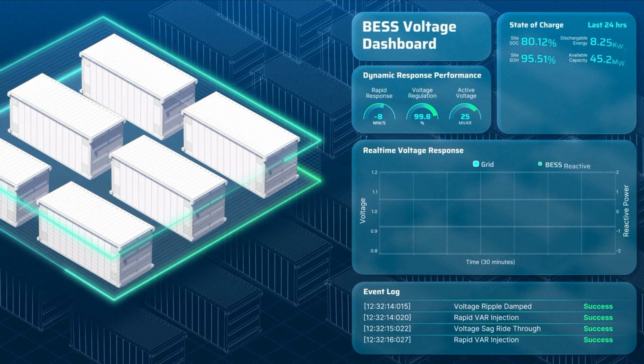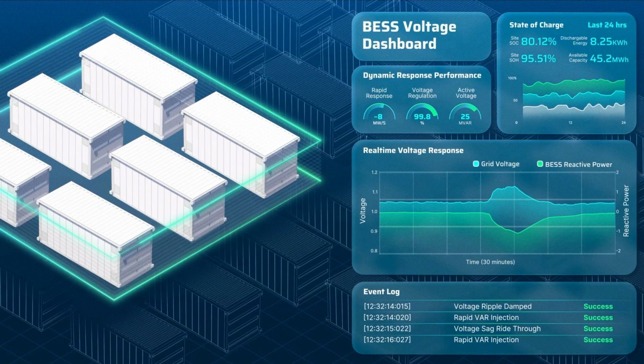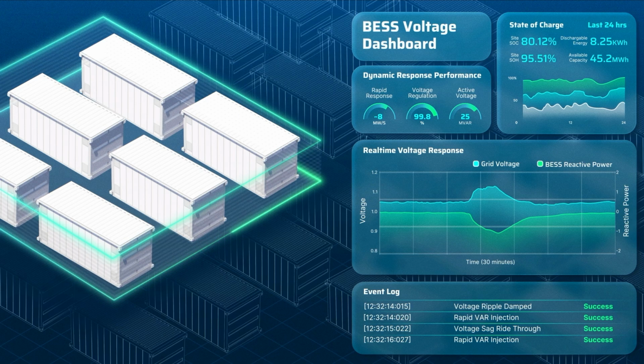But they lean on these massive battery reserves as a digital safety net. These systems provide active, real-time voltage support, as well as what engineers call virtual inertia, reacting in milliseconds to inhale excess voltage or stabilize a dropping frequency. They smooth out those minor ripples before they have the chance to trigger a cascade. Both have already used their battery fleets to successfully ride through voltage dips that might otherwise have led to similar blackouts.